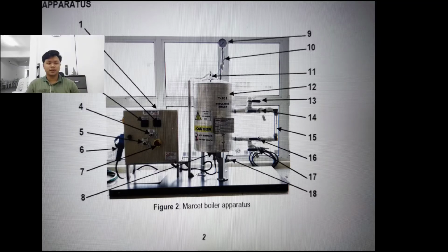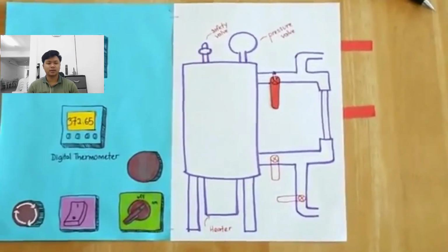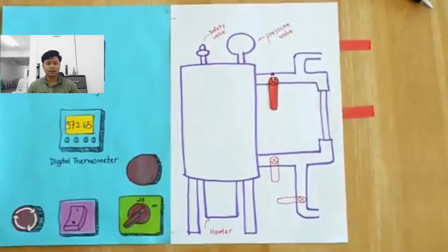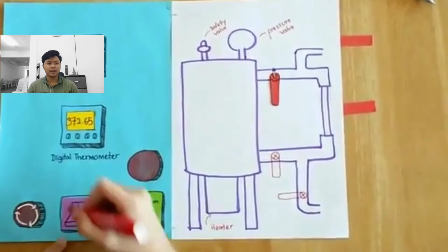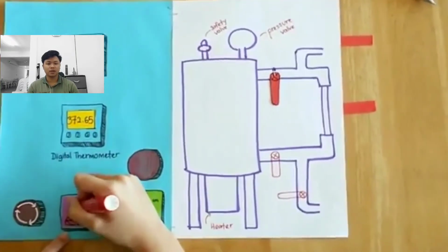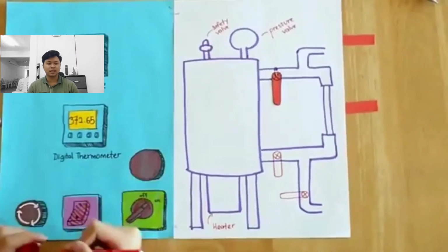For the procedure, start up the boiler. The first step is to perform a quick inspection to ensure that the unit is in proper operating condition. Connect the unit to the nearest power supply. Open valves labeled MVB 101, MVB 102 and MVB 103, located near the side glass.